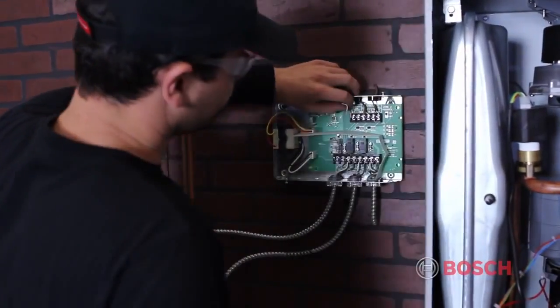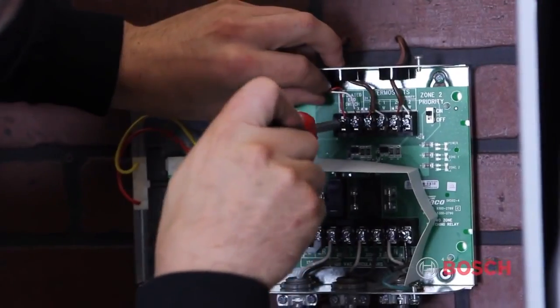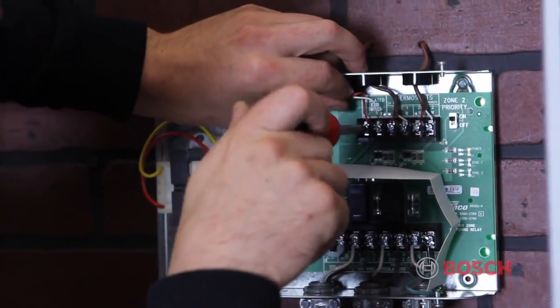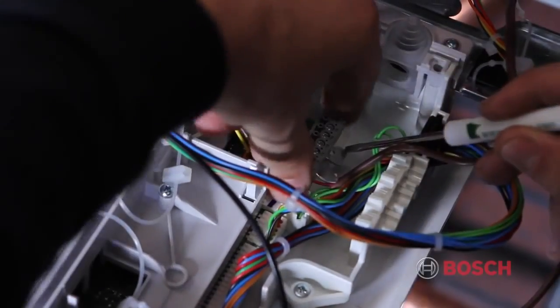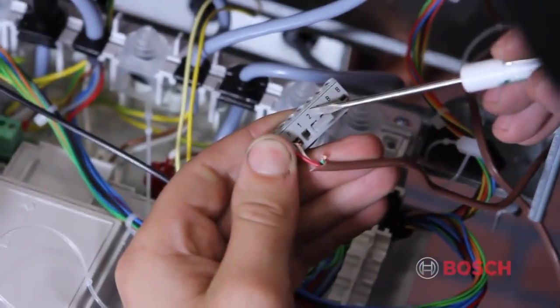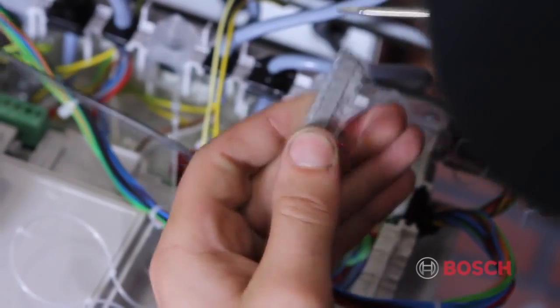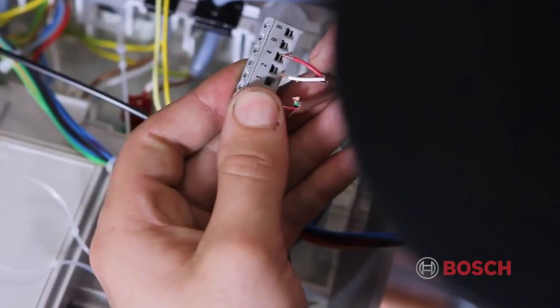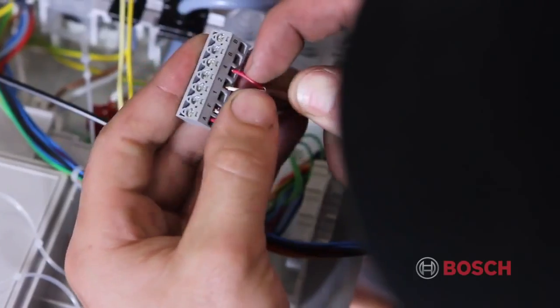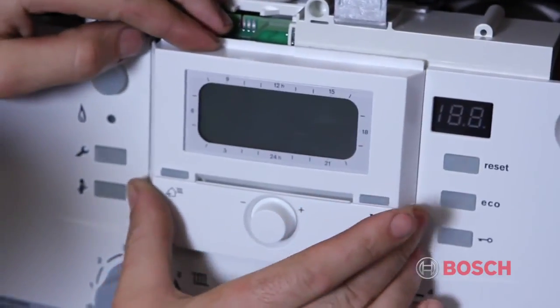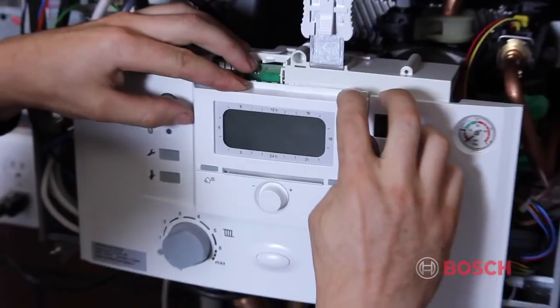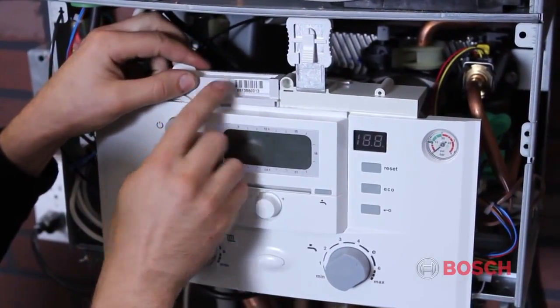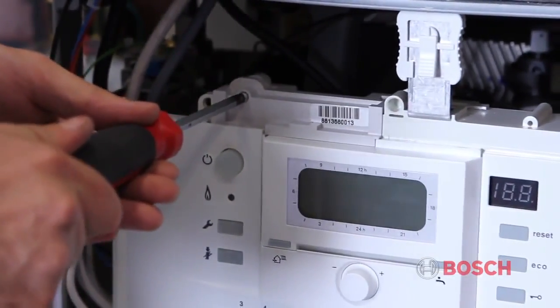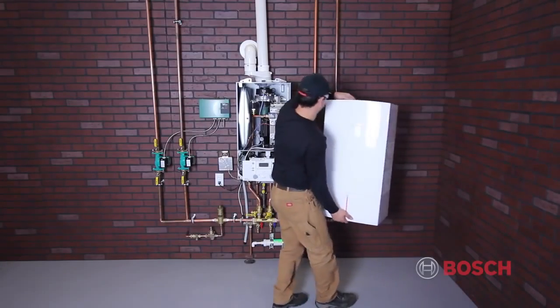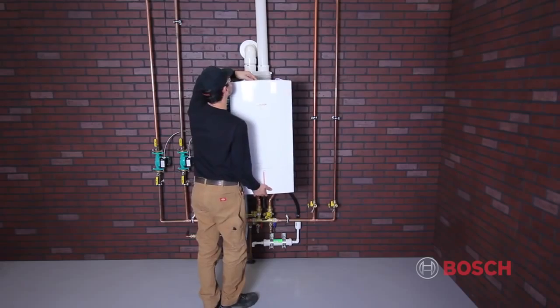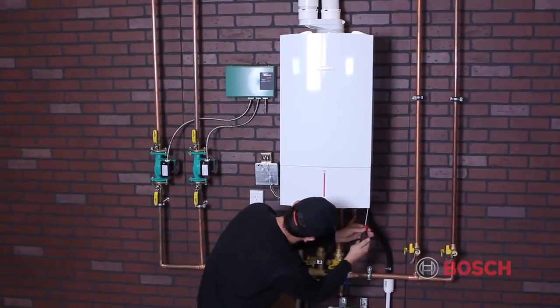In order to wire the system, connect 18-gauge 2-conductor wire to the isolated end switch on the zone control panel. Remove the jumper between pins 2 and 4 on the boiler Heatronic control panel. Run this wire to the 2-4 connection on the low voltage terminal strip. This system runs on pure outdoor reset without room feedback on the heating curve. The FW200 installed on the boiler adjusts the heating curve according to the outdoor temperature. The third-party room thermostats turn the boiler and the zone pumps on and off based on the conditions in the living space.